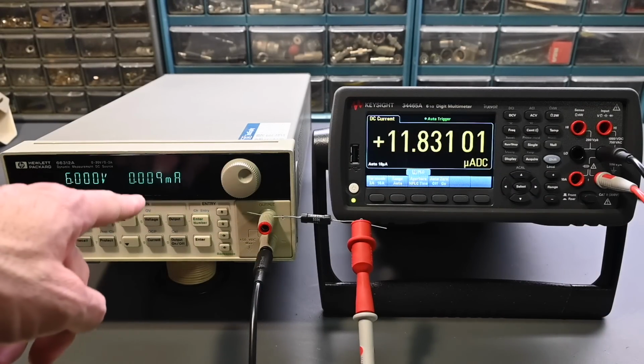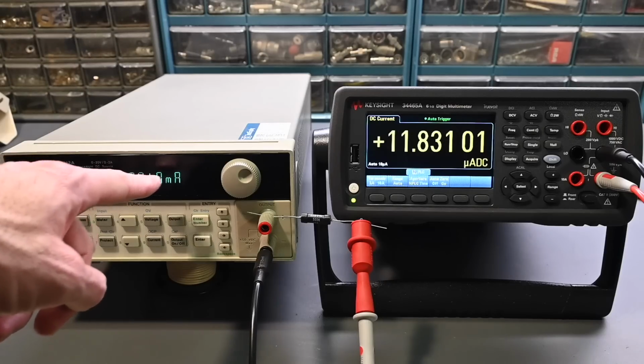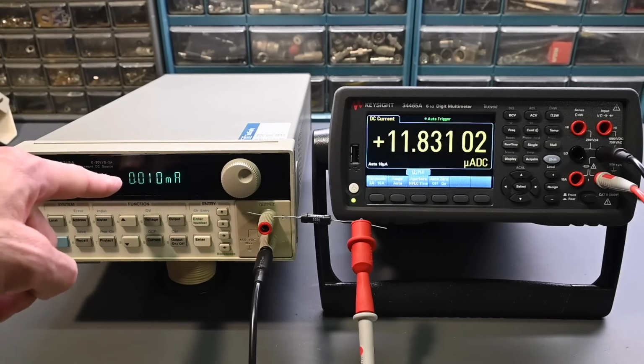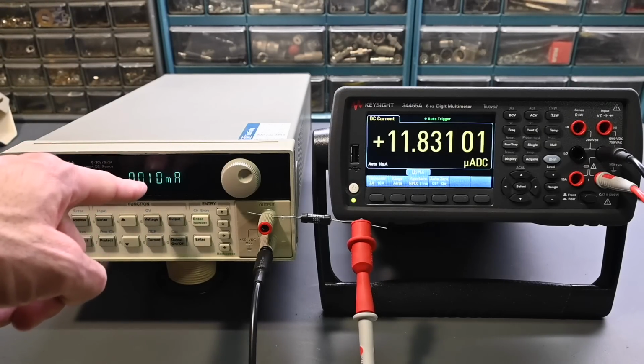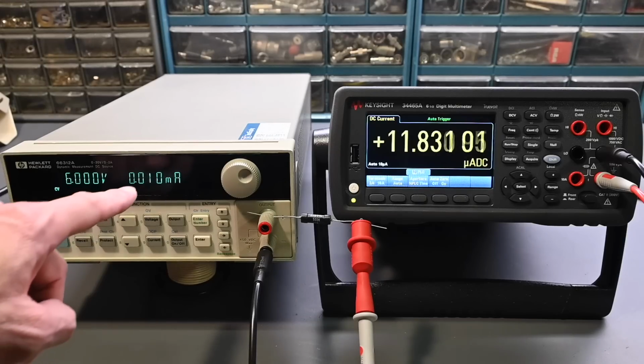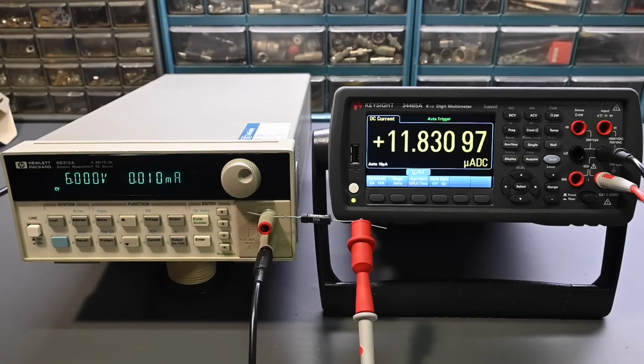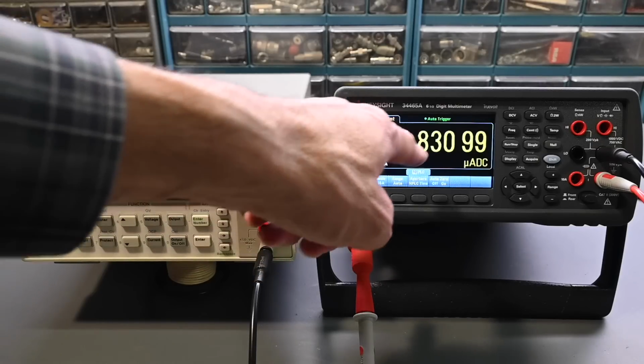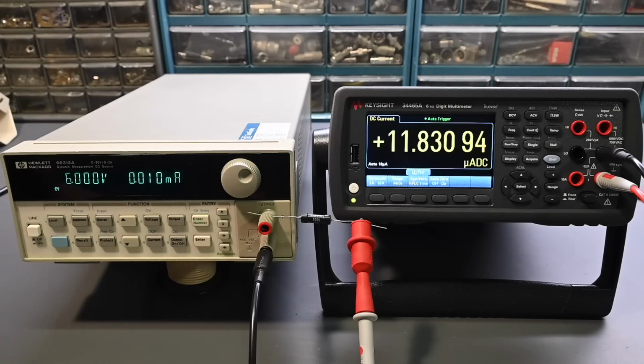This is measuring, it says here, this is in microamps, so it says milliamps, but the decimal point's right there, so it's 0.010, so that's 10 microamps. Fluctuates ever so slightly, but pretty constant, right about 10 microamps. And over here, this is reading directly in microamps, and you can see it's 11.8 and some change. So essentially about 1.8 microamps difference, and that's really, really close. 1.8 microamps is an extremely small value, so very happy with the results.